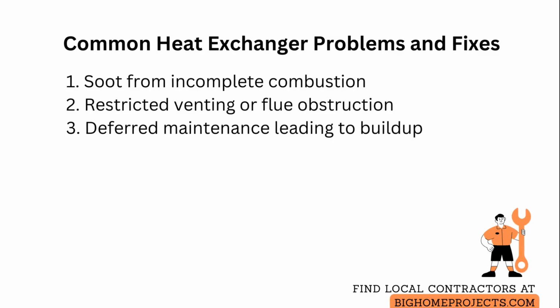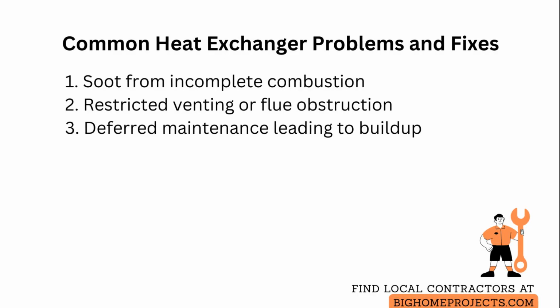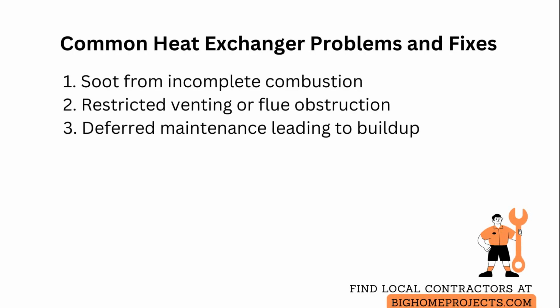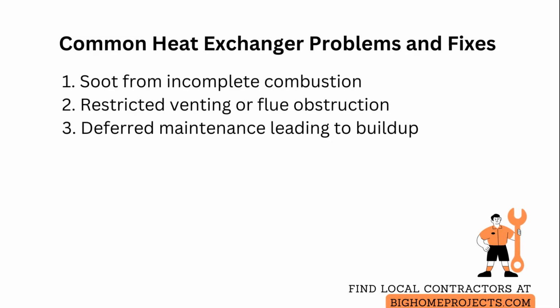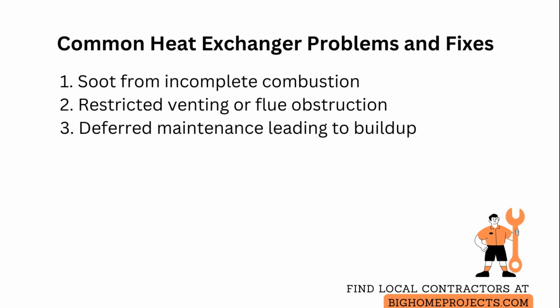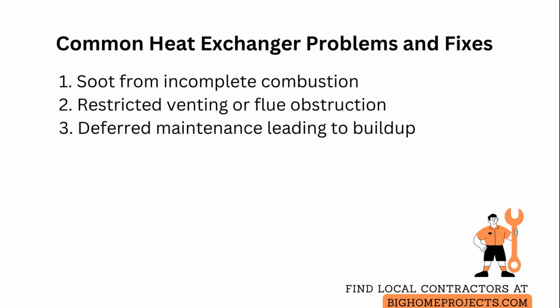Another frequent problem is restricted venting or flue obstructions that reduce draft and cause gases and particulates to linger. Clear the vent, confirm proper slope and pitch, and measure flue draft during operation to ensure safe exhaust flow. Third is deferred maintenance, where small buildups become severe over time. Implement a scheduled inspection and cleaning interval based on operating hours and manufacturer recommendations, so problems are caught early and components are replaced before failure.